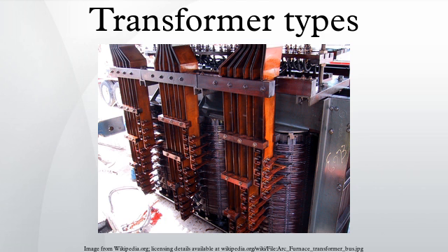Grounding transformer. Grounding transformers are used to allow 3-wire polyphase system supplies to accommodate phase-to-neutral loads by providing a return path for current to a neutral. Grounding transformers most commonly incorporate a single-winding transformer with a zigzag winding configuration but may also be created with a wye-delta isolated winding transformer connection.